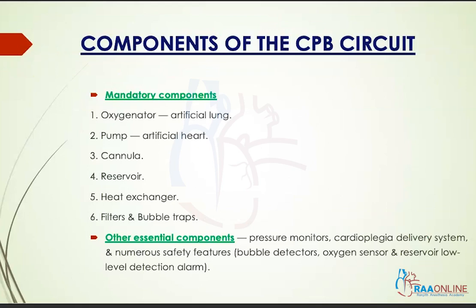The components of the cardiopulmonary bypass circuit include the mandatory components: the oxygenator, which functions as the artificial lung; the pump, which functions as the artificial heart; the cannulae; the reservoir or venous reservoir; the heat exchanger, which helps to maintain temperature; and filters accompanied with bubble traps, which prevent systemic embolization of any air that has entered the circuit. Other essential components include pressure monitors, the cardioplegia delivery system, and numerous safety features like bubble detectors, the oxygen sensor, and the reservoir low-level detection alarm.